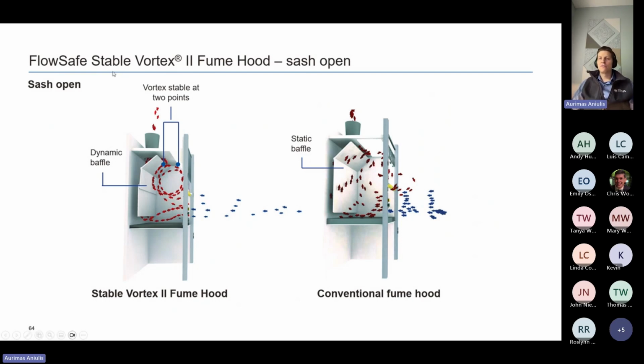So FlowSafe was born out of one gentleman's twin brother dying in a fume hood accident, and him being an engineer, he looked at it real hard and came up with a very interesting proposition. He said, well, if you can't get laminar flow, the next best thing is a stable rotating air pattern which simultaneously pulls in fresh air and exhausts any contaminants in that workspace. By just changing the geometry of the hood and modulating these dynamic baffles, we are able to contain and ensure that that vortex is always present and spinning, and we can alarm and warn people when they're approaching those conditions where that vortex would break down or something would trigger an unsafe condition.